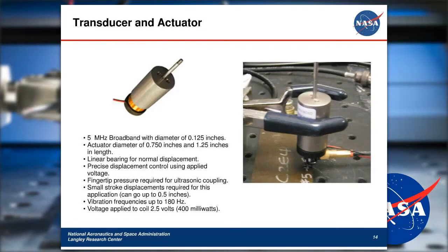Okay, so here's just a close-up description of the transducer and actuator. The transducer we're using is a 5 megahertz broadband unfocused transducer with a diameter of about 1/8 of an inch. The actuator diameter is about 3/4 of an inch and is about 1 1/4 inches in length. You'll see that there's a rod that sticks up from the actuator, and this is a linear bearing for normal displacement. So what this does is keeps the transducer normal to the surface of the part that we're inspecting.